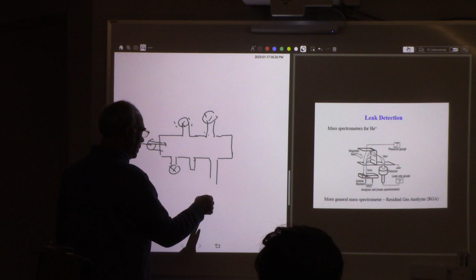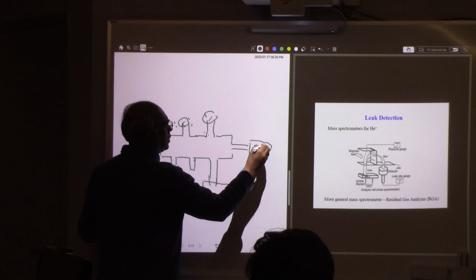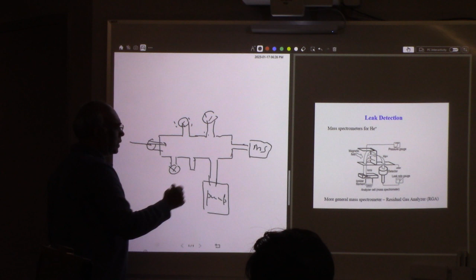So this is connected to a mass spectrometer and a pump. After pumping the system, even while pumping, I can spray helium on a joint. If there's any leak, helium will creep through, and that will be detected by the mass spectrometer. These mass spectrometers have an audible sound, and if there's a leak it gives a very annoying noise. That way you can tell where the leak is.